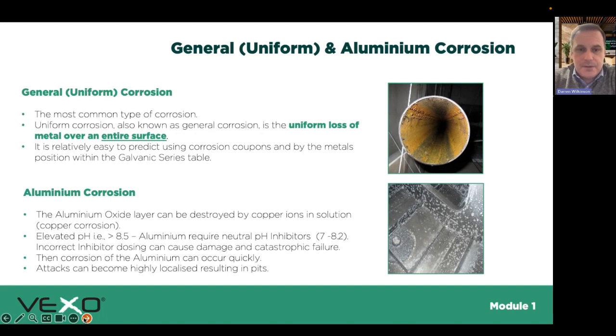And then there's aluminium corrosion. So a huge amount of commercial boilers that are specified, and I know we are moving to heat pumps, and we should be moving to heat pumps or other technologies, certainly. But again, aluminium is a great metal in terms of its ability to transfer heat most efficiently. Unfortunately, in a water quality situation, aluminium is very sensitive to pH in particular. A lot of common corrosion inhibitors used by water treatment companies are generally alkaline based, and aluminium requires neutral pH treatment. It needs to be maintained below 8.5. Anything over that, we're going to start seeing degradation of the actual aluminium, and you can see boiler failures typically as well, quite common.